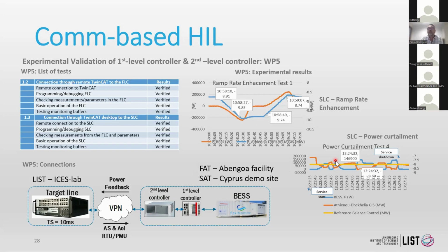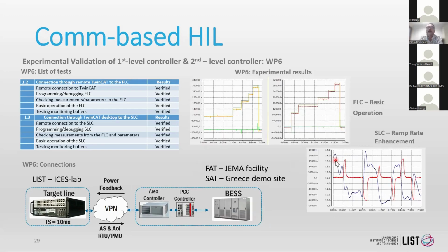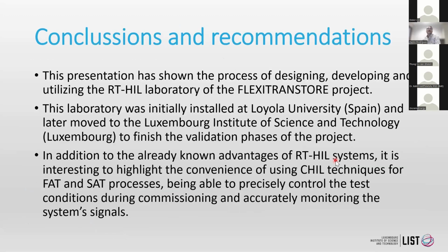The same happened with Greece, with the Work Package 6 demonstrator. We were generating the signals in Luxembourg, and in Greece, we were able to send signals for the buses and references in order to test the batteries that were installed in the substation of the wind power plant. That allowed us to make, as you can see here, many different tests that are not possible to conduct in reality, because operating conditions in a real system are not controllable or manageable. So this was what we did in this project.